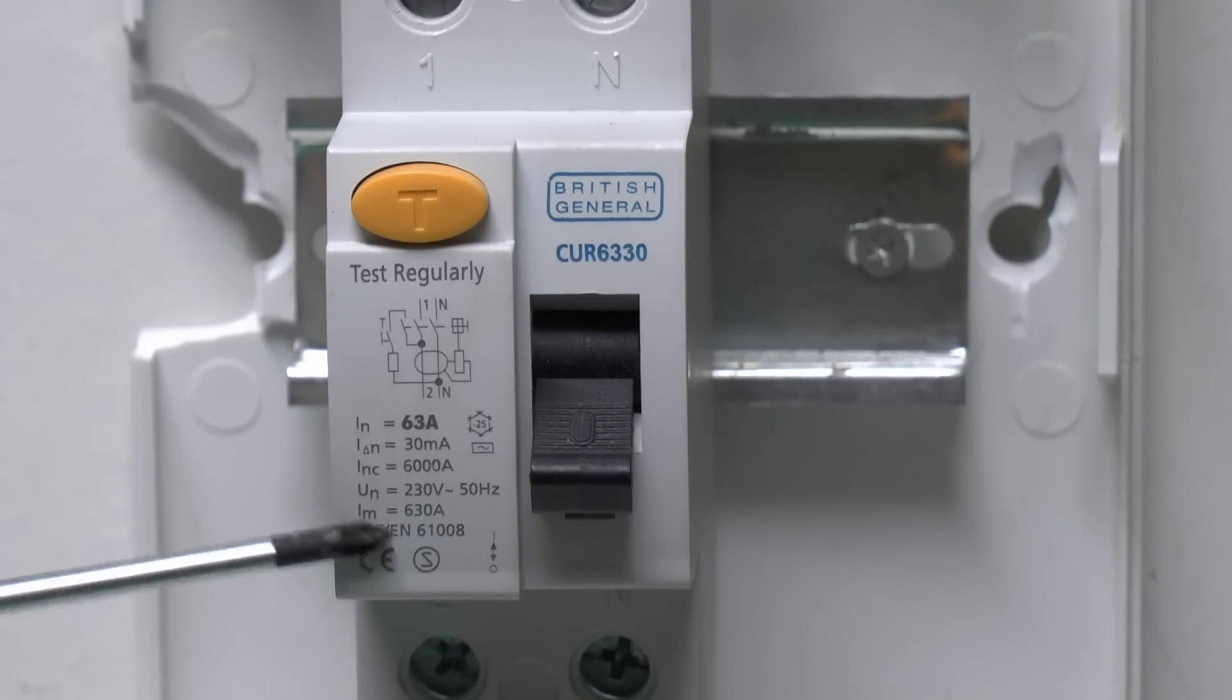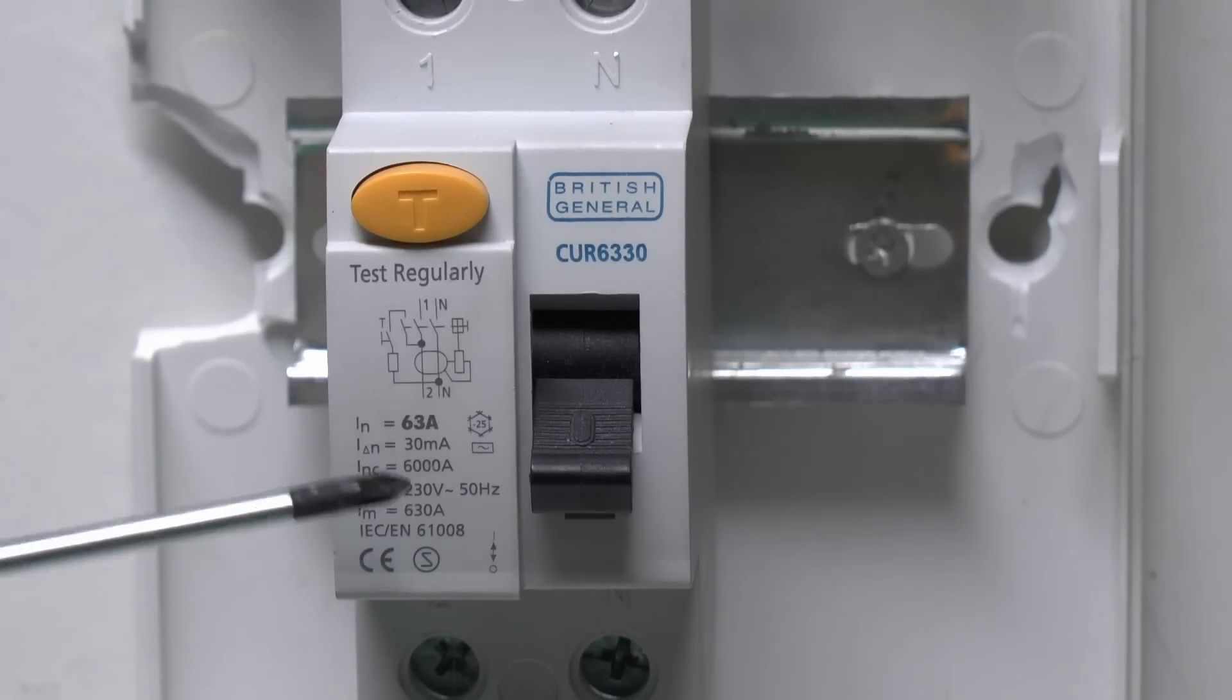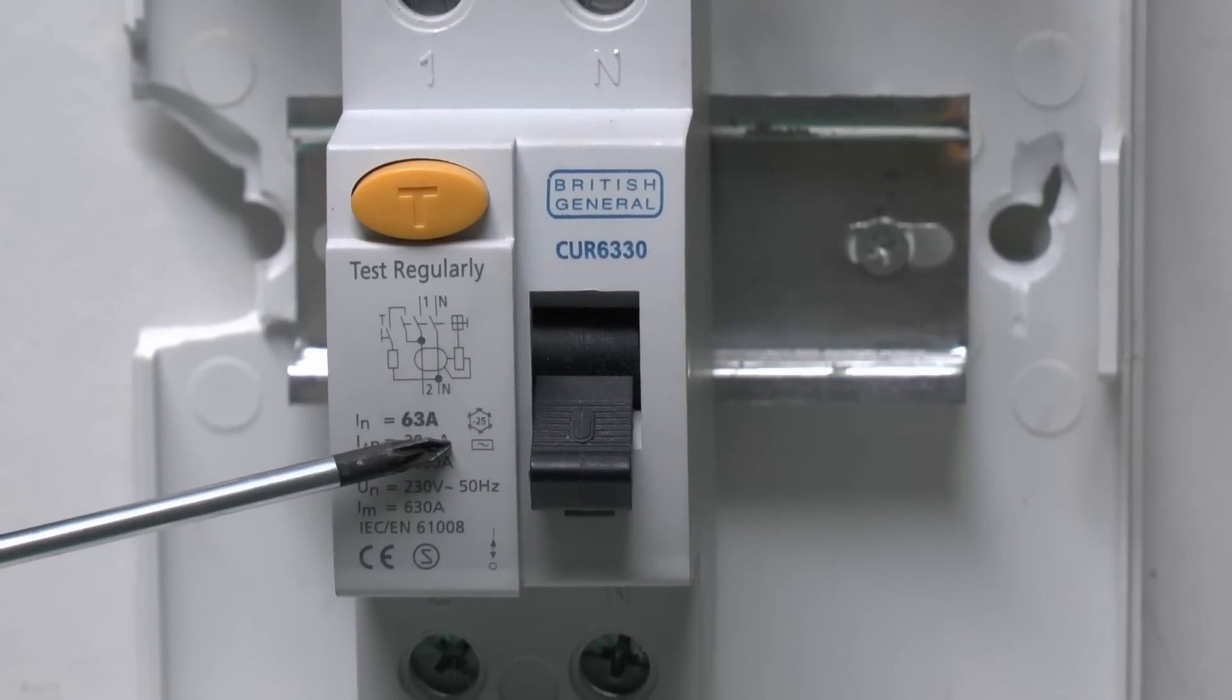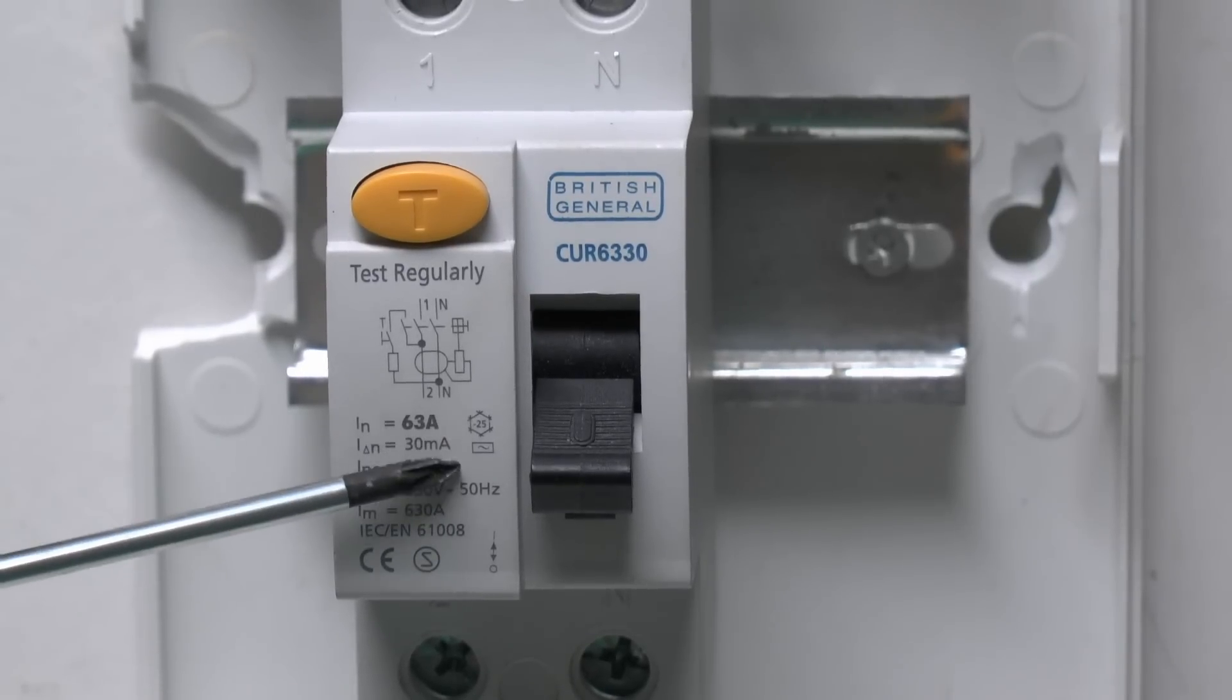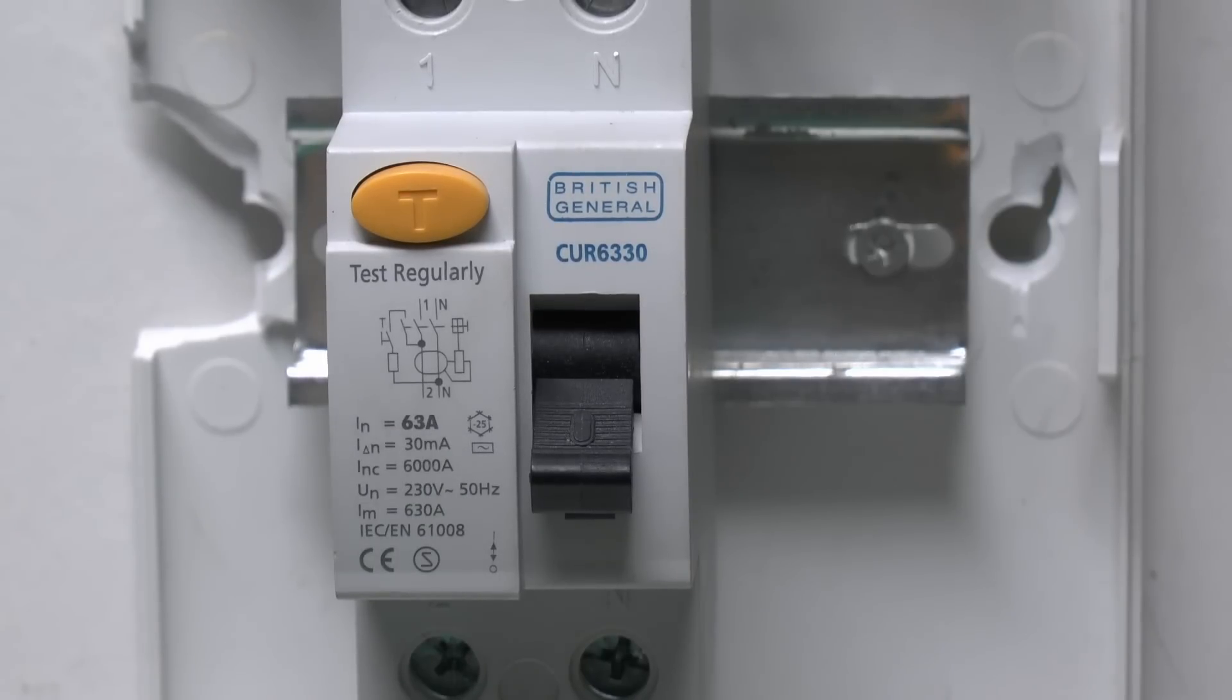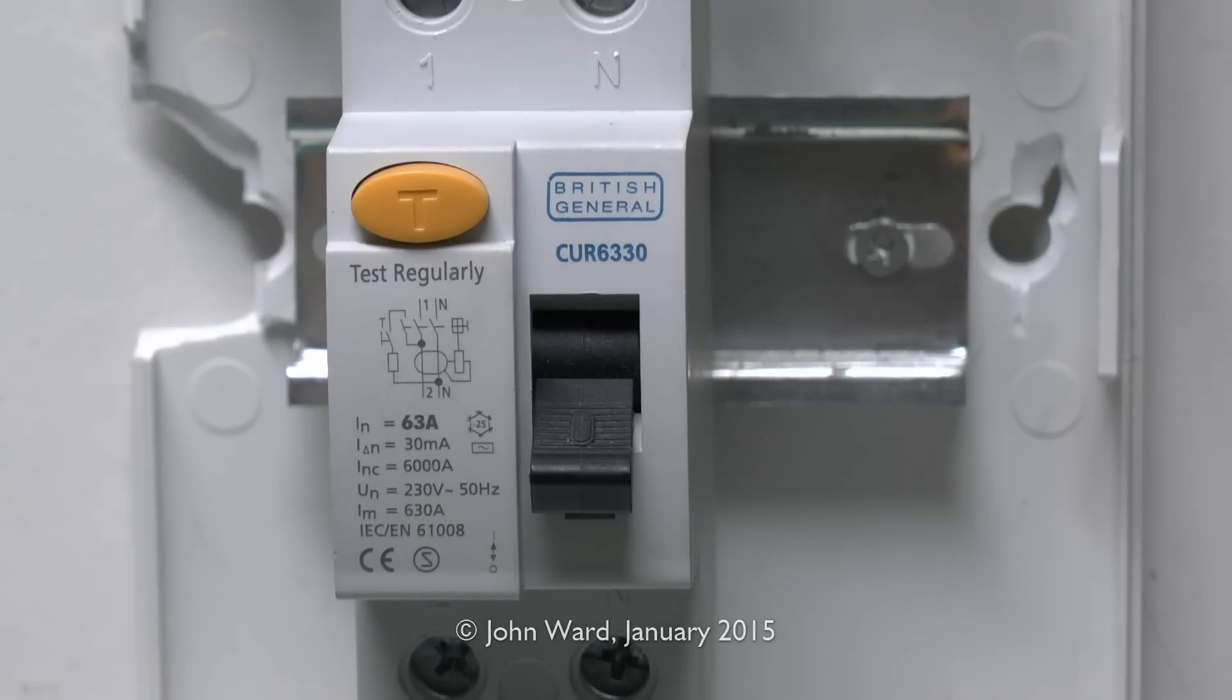And then the standard to which it's made here and the CE mark and so on. Then over here in this very small symbol is the type of RCD, in this case it's an AC, and it's going to have that small AC waveform inside the rectangular box. There are other types of RCD, and that's certainly significant when you actually come to test them, because you need to make sure you've selected the correct test options.